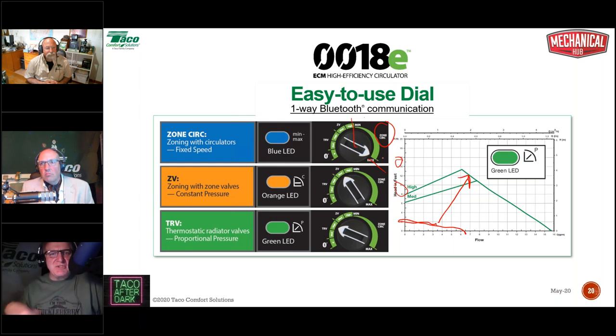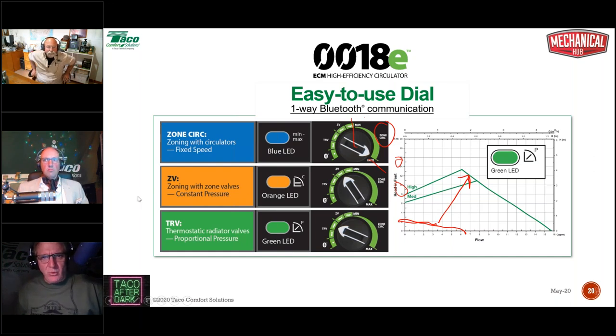When the pump's in continuous circulation and you have modulating control valves, then and only then, with a pump this size, would you use the proportional pressure mode, as we see here. And we have two settings there for medium and high as well, as we have a declining performance curve. As flow goes down, the head loss or the head pressure differential created by the circulator goes down as well, as it would in a parallel piped, you know, TRV home run type of system. So, where does that leave us?